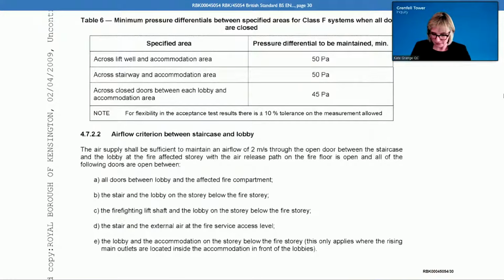Despite my reference earlier in B1 and B5, this does cross over actually, because you then have shafts rising up the building. So clearly I did, because I looked at the plans and they showed the shafts as fire resisting, not just the 30 minutes, which would have been just the means of escape standard. So you did realise that would also impose a requirement in terms of the dampers? They would need to be at least fire and smoke dampers to satisfy that requirement of being a protected shaft. Did you ever think about that?